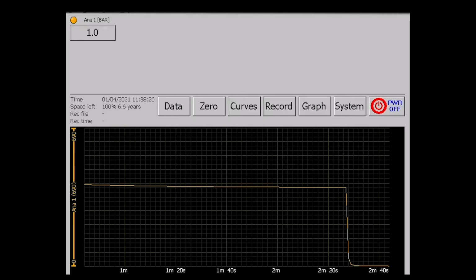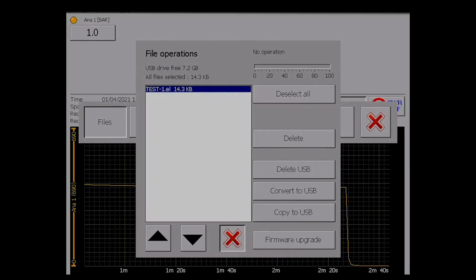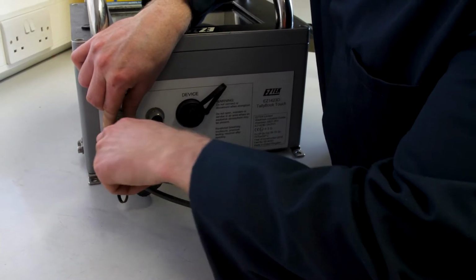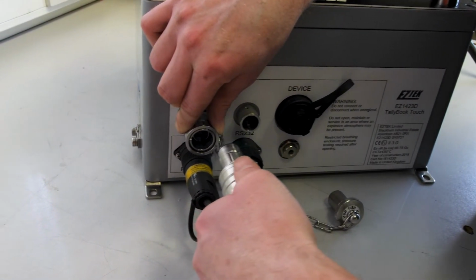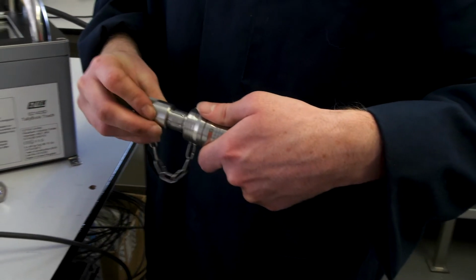Next, we should press the System button once more and then select Files, so we can prepare the files that are to be imported into TallyView. We will now select the test that we have named earlier to export, or you can select All Tests, and then press two buttons. The first is Convert to USB, which creates a CSV file, and Copy to USB, which copies over the Eztek file format. The test data is now on the Zone 1 USB, ready to be viewed using the TallyView software.